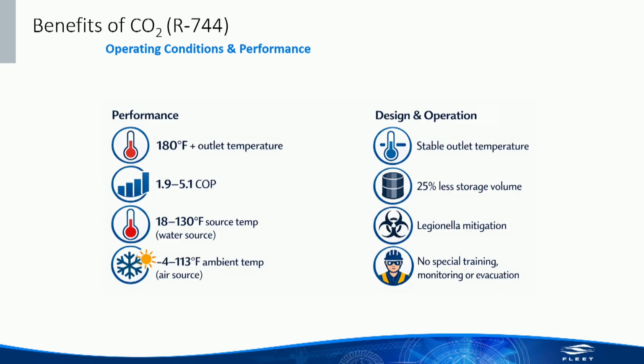Because we're able to store at 180, you may ask, why are we even doing that? Here in New York, space is king, I think everybody knows that. Being able to store at 180 degrees allows us to use less overall storage. You're going to get more BTUs per gallon at 180 degrees than you would at 140. That's going to allow us to reduce the overall storage capacity in most of our systems by about 25%, which is going to save space as well as first cost.